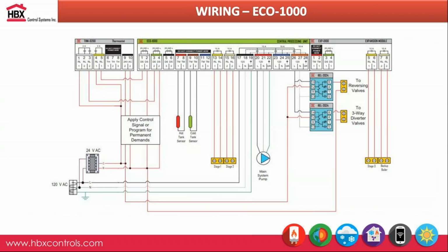In terms of wiring, here's a basic schematic of how you would wire up an Eco 1000 to an EXP100. The EXP100, again, is getting its power from the Eco 1000, which is real nice. And it just connects using a 32-pin connector. Your first 3 inputs are for your heating and cooling demands. For this example, we're just using our thermostats, but you can use anyone's thermostats to control the heating and cooling demands.